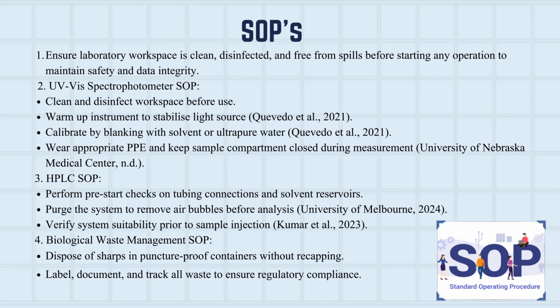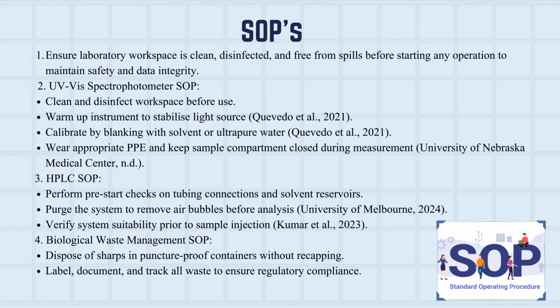SOPs. First, ensure the laboratory workspace is clean, disinfected, and free from spills before starting any operation to maintain safety and data integrity. For the UV spectrophotometer, clean and disinfect the workspace before use. Warm up the instrument to stabilize the light source, then calibrate it by blanking with solvent or ultra-pure water. During measurement, wear appropriate personal protective equipment and keep the sample compartment closed.